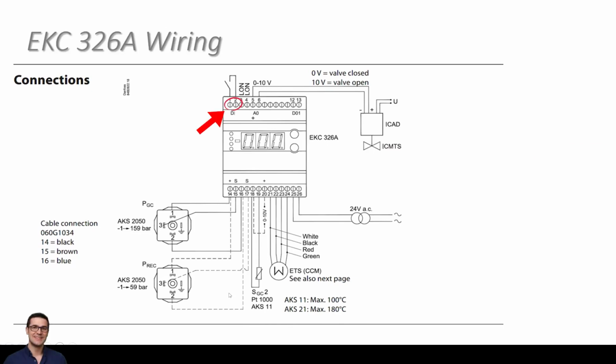So Chris, the 1 to 2, for example, if that was left open, if someone didn't have that closed on a closed relay, that wouldn't start up, correct? That's a good point. Yeah, if you're not using this for the intended purposes here, you actually just want to jump those 2 terminals out. It's kind of just in a run mode all the time. Yeah, is one way to describe that. But yes, that's correct. If you're not using this for some sort of a shutdown signal, just a little jumper wire between those 2 terminals so that you're not running into anything.